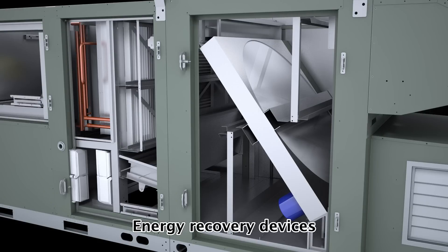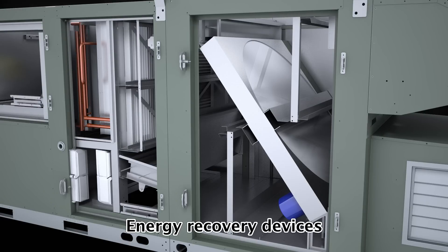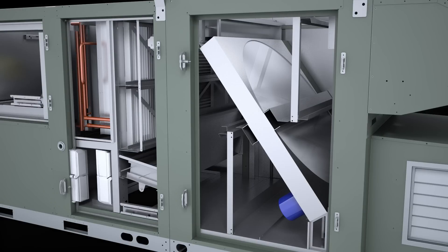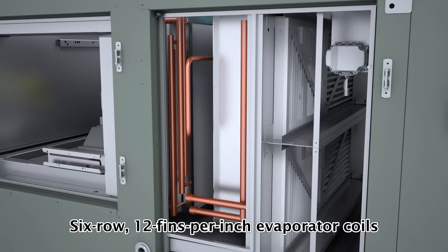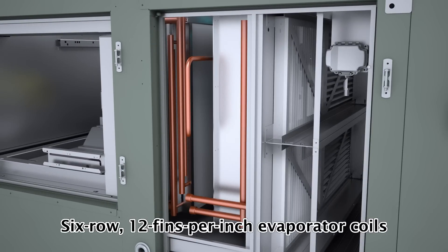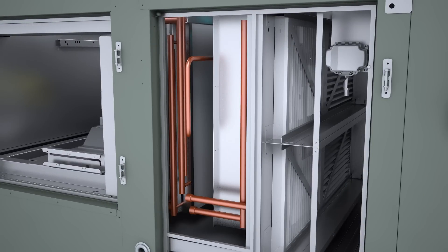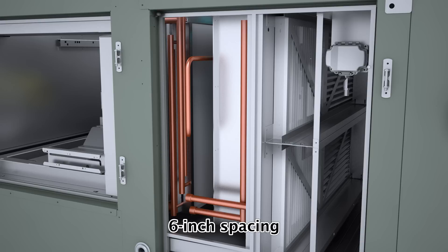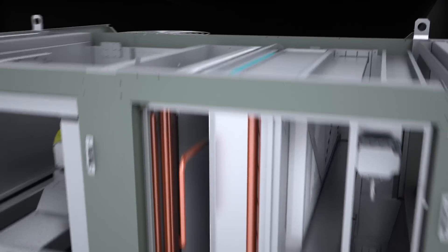Energy recovery devices with high recovery efficiency ratios and bypass dampers that precondition outdoor air. Six row, 12 fins per inch evaporator coils to quickly dehumidify outdoor air. Six inch spacing between evaporator coils and hot gas reheat coils to prevent moisture re-evaporation back into the occupied space.